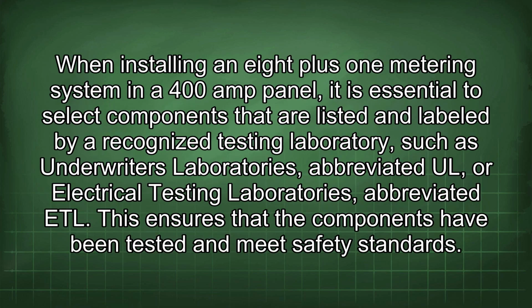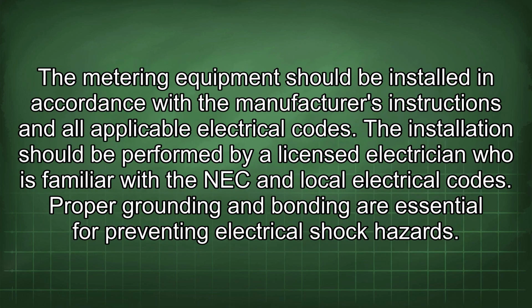When installing an 8+1 metering system in a 400 amp panel, it is essential to select components that are listed and labeled by a recognized testing laboratory, such as Underwriters Laboratories, abbreviated UL, or Electrical Testing Laboratories, abbreviated ETL. This ensures that the components have been tested and meet safety standards. The metering equipment should be installed in accordance with the manufacturer's instructions and all applicable electrical codes. The installation should be performed by a licensed electrician who is familiar with the NEC and local electrical codes.